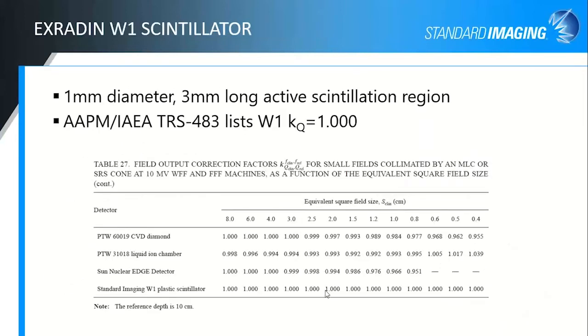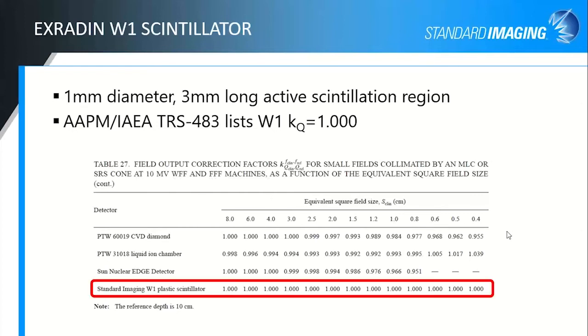So I mentioned the W1 is the 1 millimeter diameter, 3 millimeter long scintillator. And in the TRS 483 publication, they have a lot of tables of correction factors for various energy beams as a function of field size. And in every single table where the W1 shows up, every single correction factor here is unity. And that's because we really are truly water equivalent for this detector.